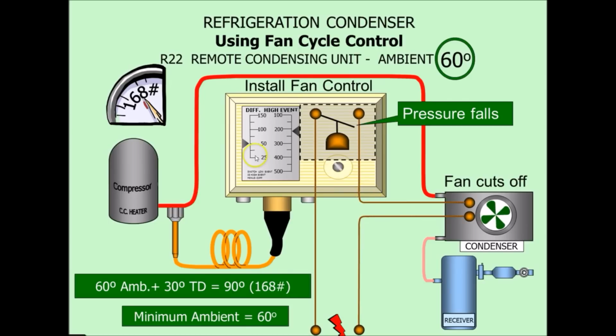All right, so the next thing you want to look at is the pressure settings. There'll be screws on the top of this unit that'll adjust these pointers to the point that you want. Now, let's take a look at the differential. This is the difference in pressure between cut-in and the cut-out pressure. You want to keep that between 30 and 50 PSIG.